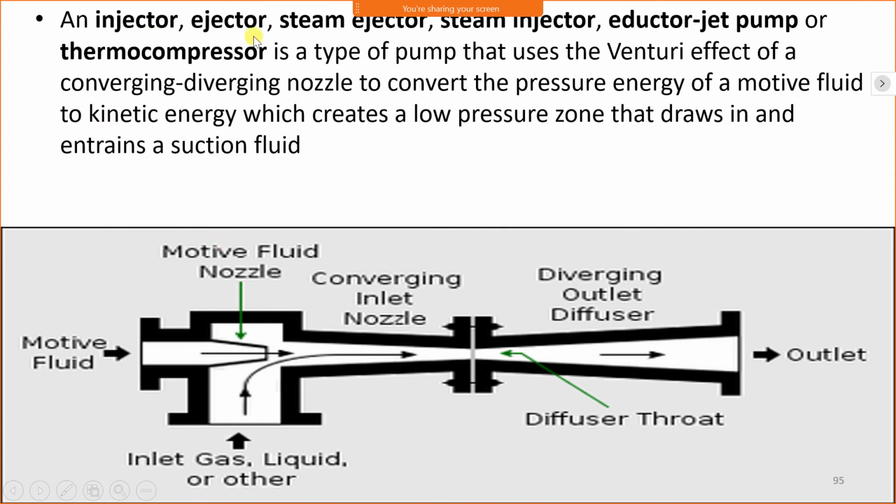An injector is also called a steam injector, steam ejector, eductor, jet pump, or thermocompressor. It is a type of pump that uses the Venturi effect of a converging-diverging nozzle to convert the pressure energy of a motive fluid to kinetic energy, which creates a low pressure zone that draws in and entrains a suction fluid.